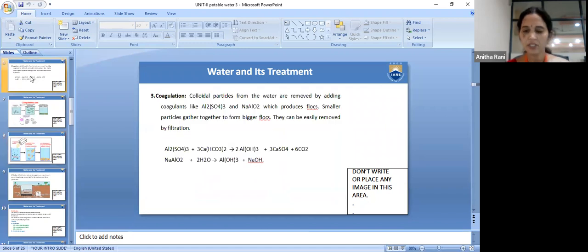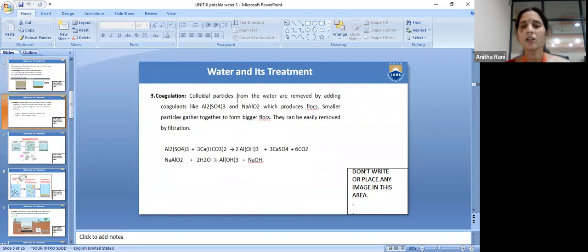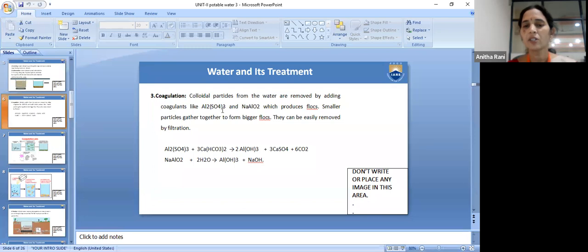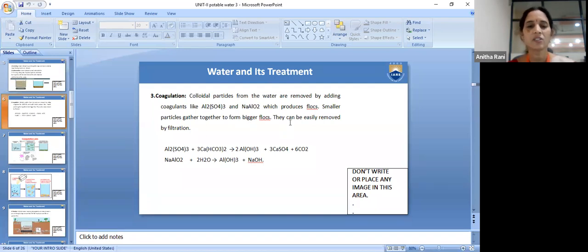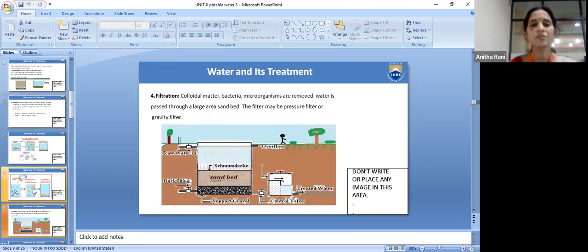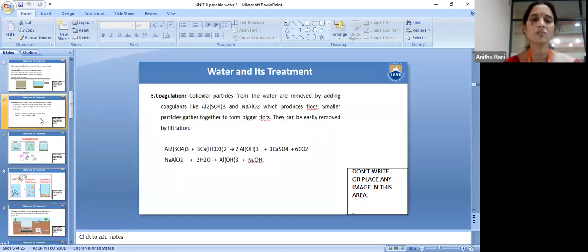To summarize coagulation: to remove colloidal particles, we add coagulants like aluminum sulfate and sodium aluminate. These form aluminum hydroxide flocs that attract negatively charged particles. Neutralization takes place, forming bigger flocs that settle at the bottom of the tank. Then we go for filtration to remove the settled material.